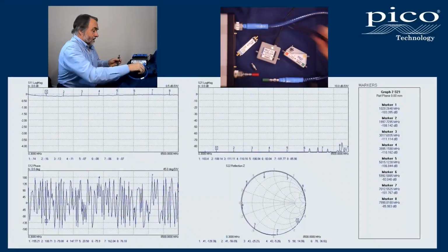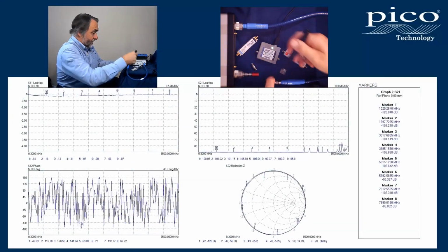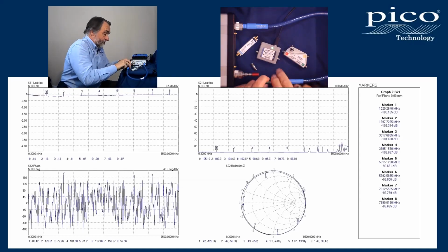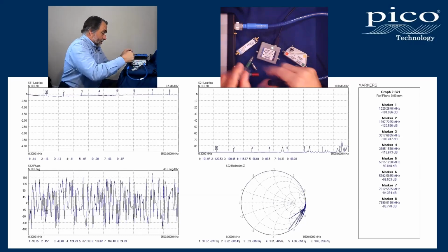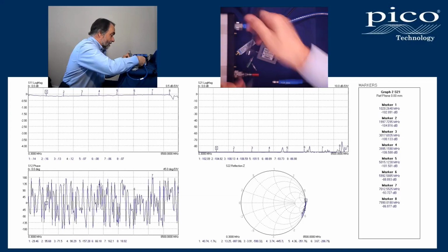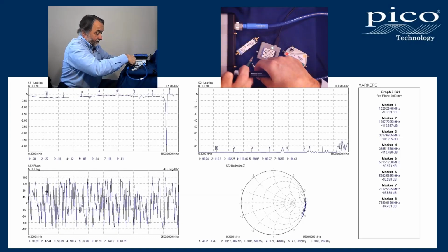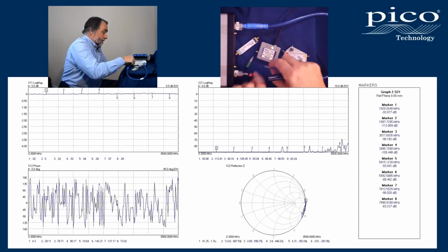And then, as I said earlier, we want to measure the through as well. What the through is going to give us is a very good match in the center of the Smith chart. It's going to be a measure of the match of both the adapter and of the correction of the VNA, so the residual match of the VNA. So let's remove these two pieces here. Open. Short, and let's fit the through.